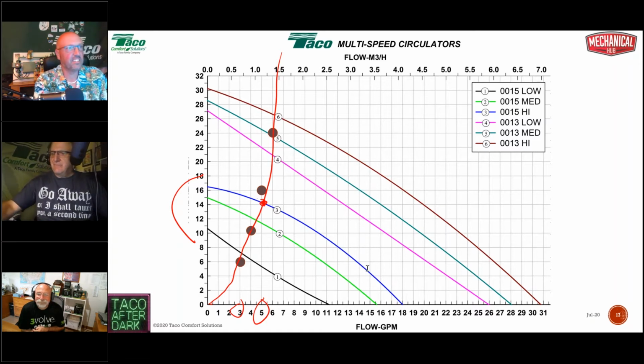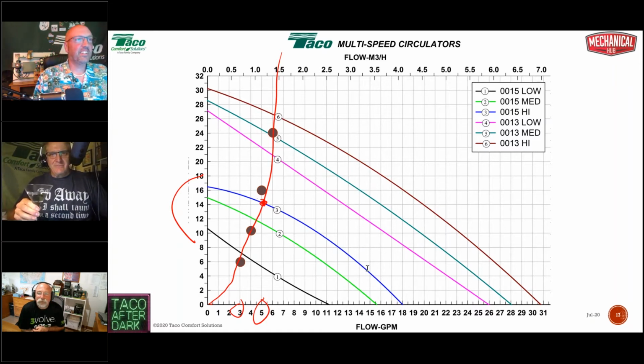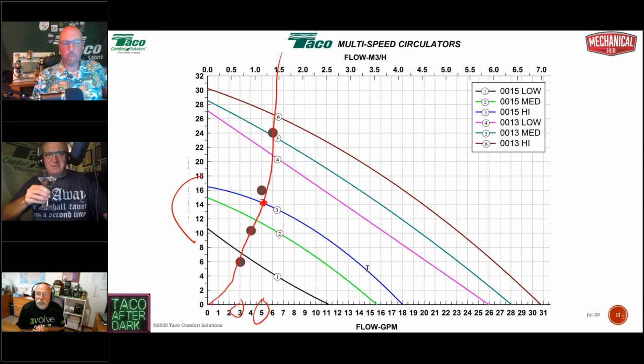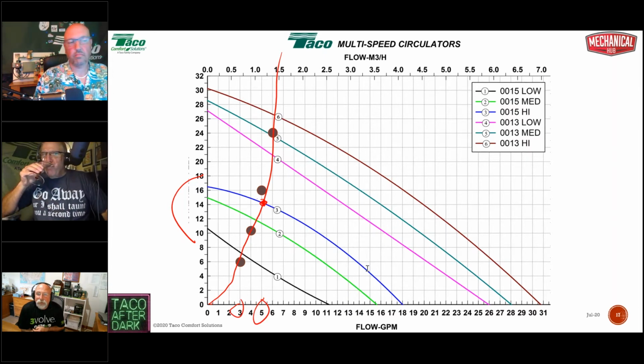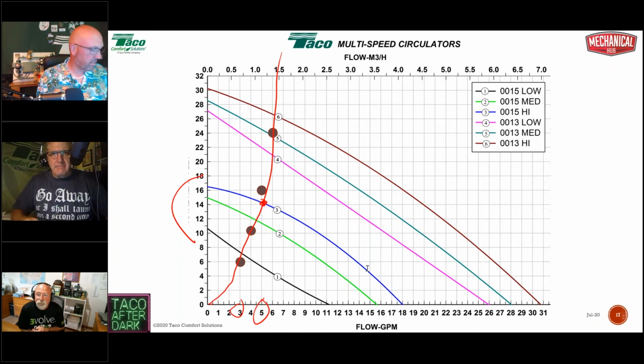That's right, that's right. Dan Cook's got a good one. What does Mr. Cook have to say? I ask contractors how they know the circulator size properly, and all he gets is crickets. Only one contractor has answered: I measure the delta. Hey, most high efficiency boilers give you the supply temperature and the return temperature, or the contractor can measure the delta T on a cast iron system, if they're close to their desired delta T. Would this be an accurate comment?